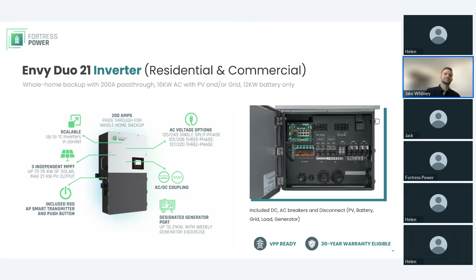Now, with the inverter, lastly, the knockouts. There's knockouts on the back side, as we can see in this image. There's one on the right side, on the left side, and then on the bottom. So again, ease of install for the wiring is pretty flexible with this inverter. The commissioning of this inverter can be done on it in person, or you can commission it remotely too, which we'll get to shortly.